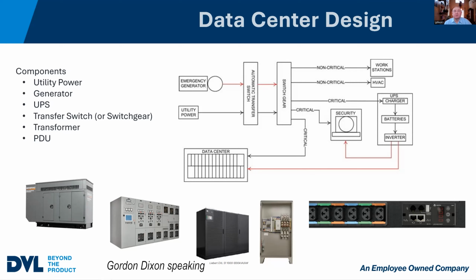Then you're going to have a transfer switch. That's so that you're not going to get dual feed. You don't want utility power and generator power or UPS power coming into your components at the same time. You're going to have a transfer switch that senses when utility power goes out, then it turns the generator on and sends the signal to the UPS to carry the load until the generator is back on. So it's kind of like an electrical traffic director.